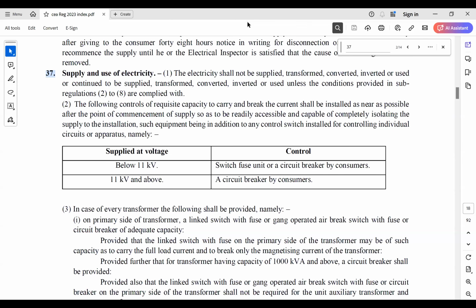While tapping the supply, that is taking the supply from the overhead line, as per DISCOM norm, the consumer has to provide a ring main unit. And then again, for the transformer which is located behind, there also you have to provide another circuit breaker. What is happening is that three circuit breakers on the HT side have come up due to all these regulations. And this not only increases the cost, life cycle cost, it becomes a burden to the MSME consumer.